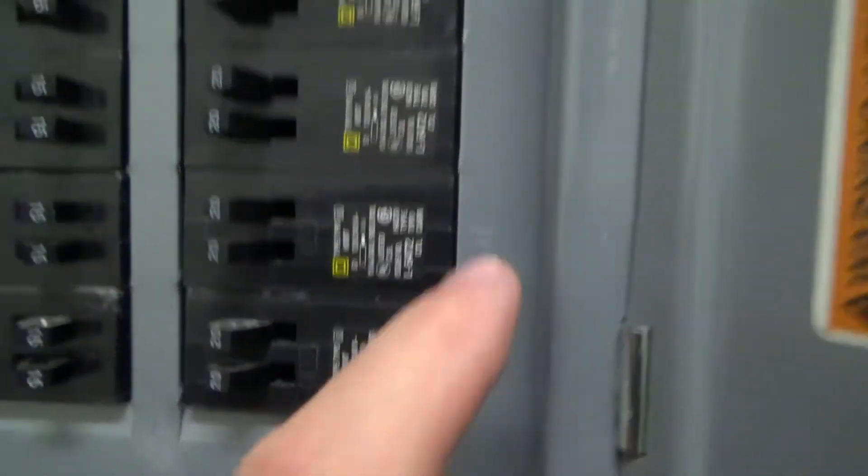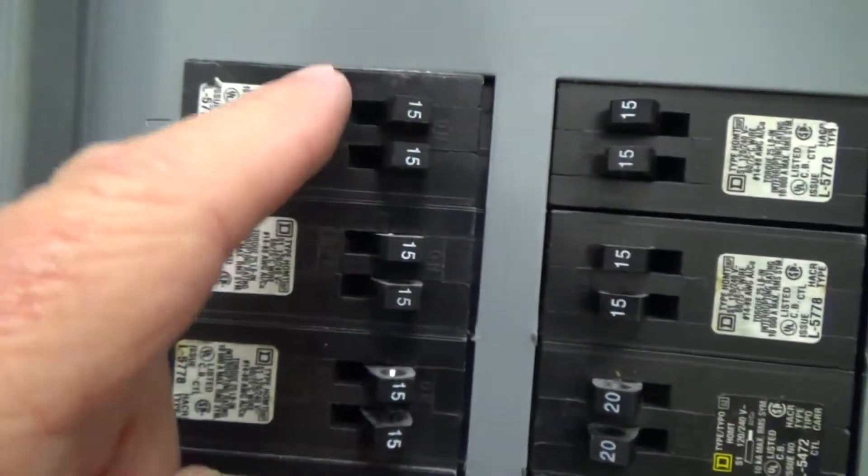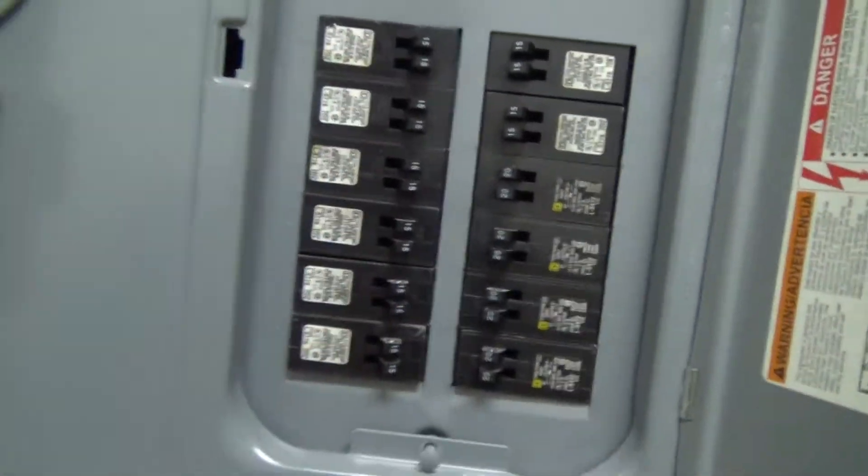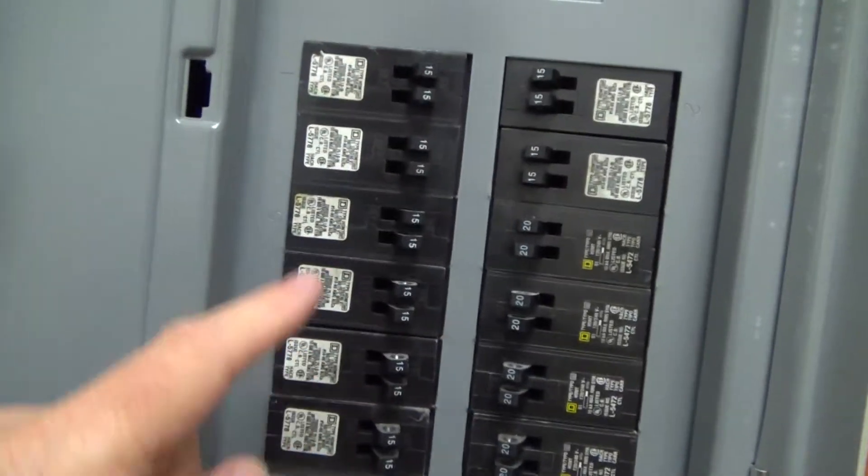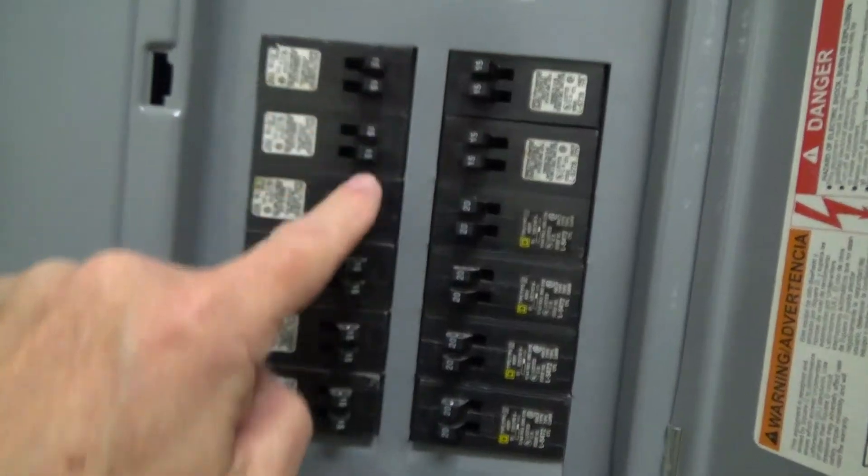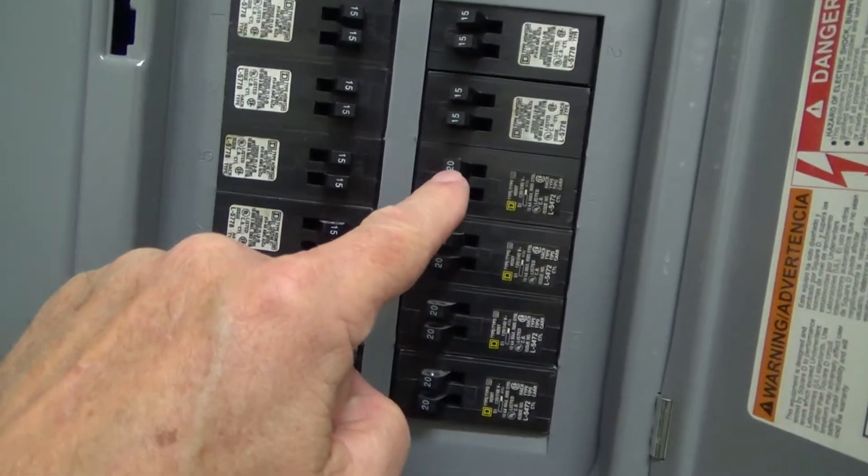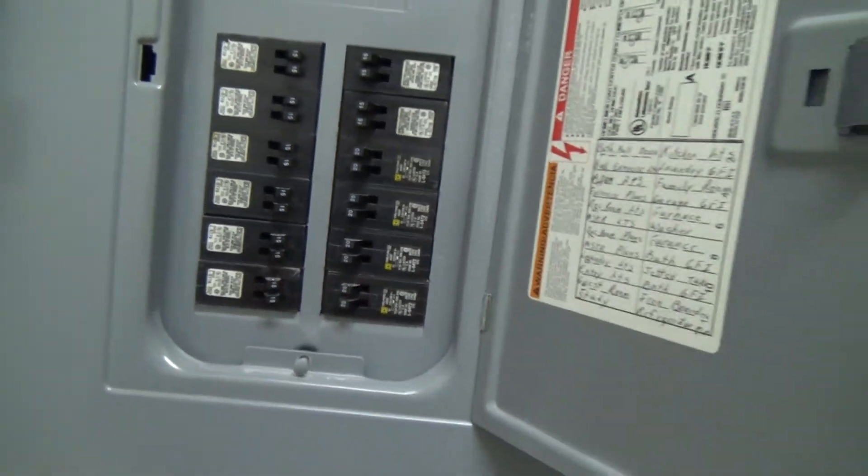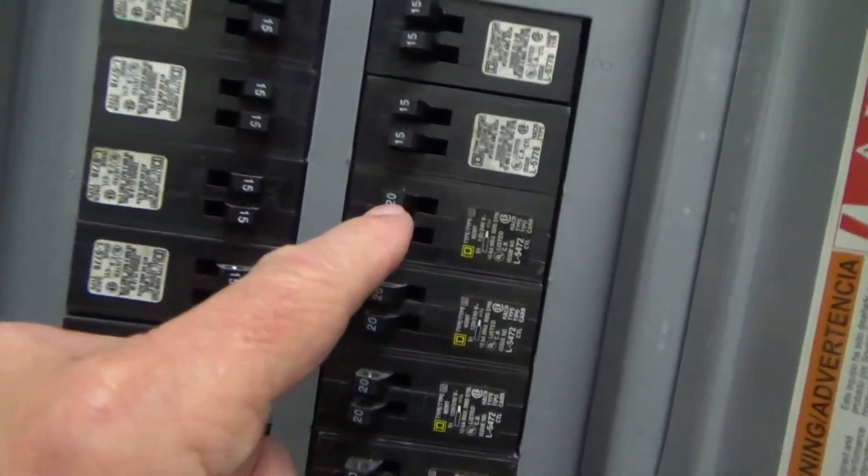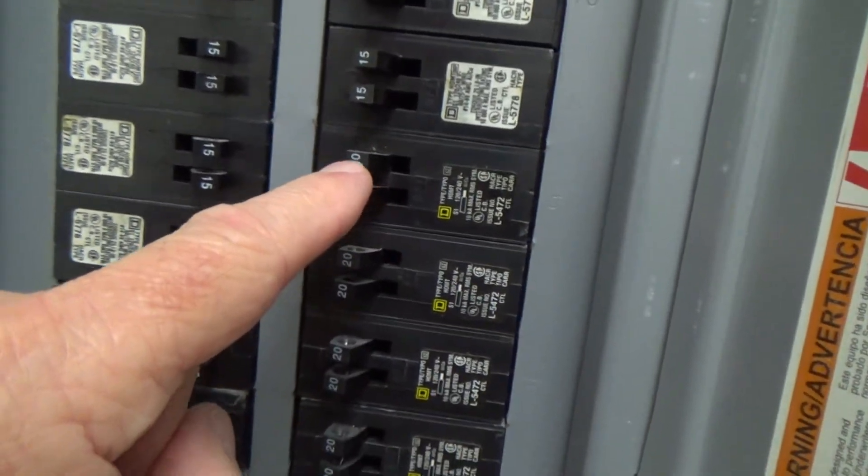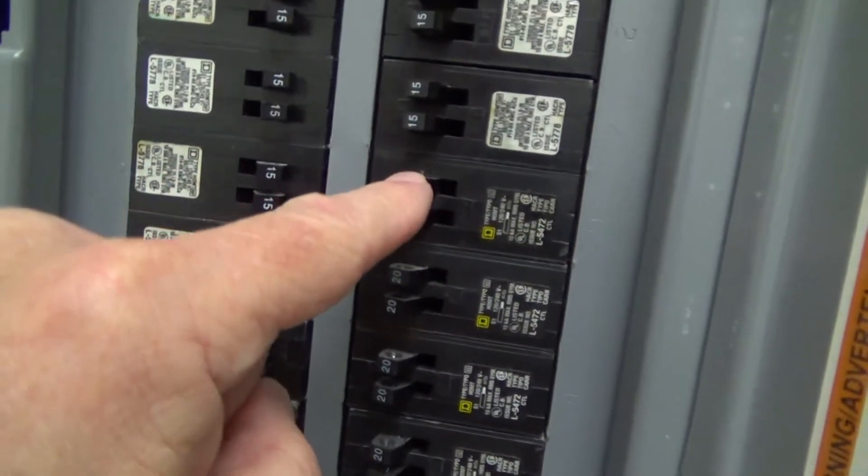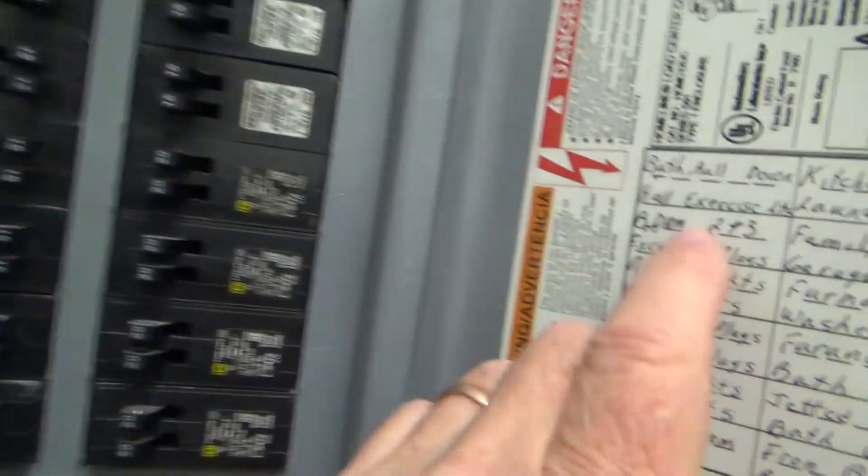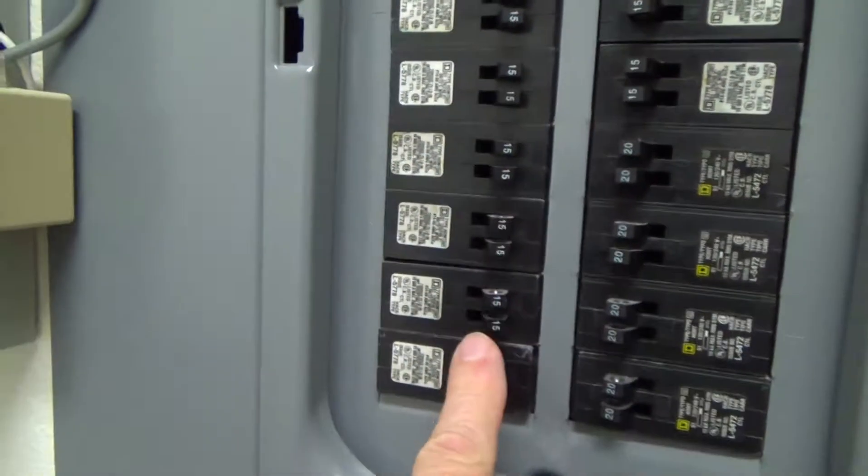We go back here and we look at that. These are all 15s, and that means all of these circuits can be run off of 14 gauge wire, 14 gauge wire for all 15 amp circuits. 12 gauge wire for 20 amp circuits. 12 gauge wire, it's a fatter wire and it's got more amps on it. It's got five extra amps than a 15 amp, so obviously you need a thicker wire for that.